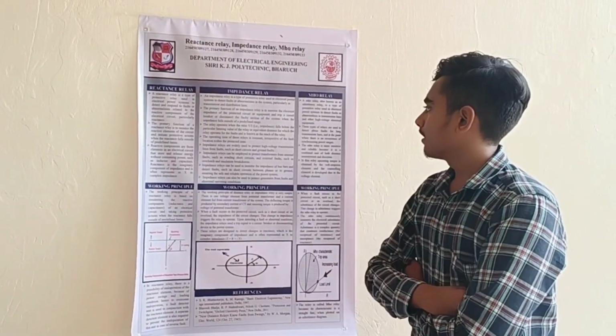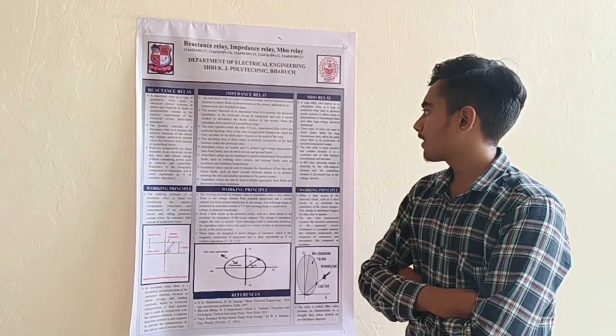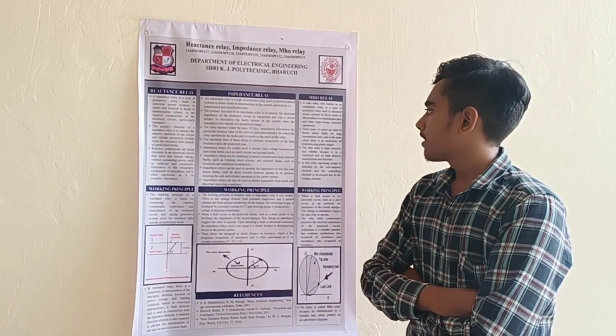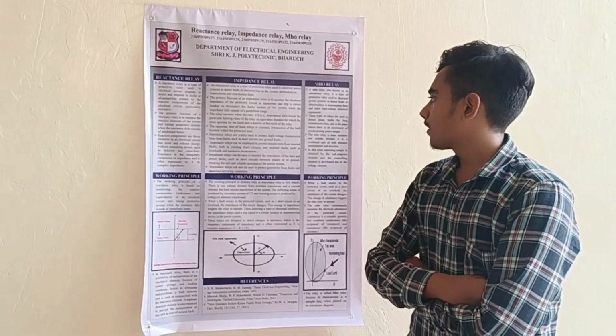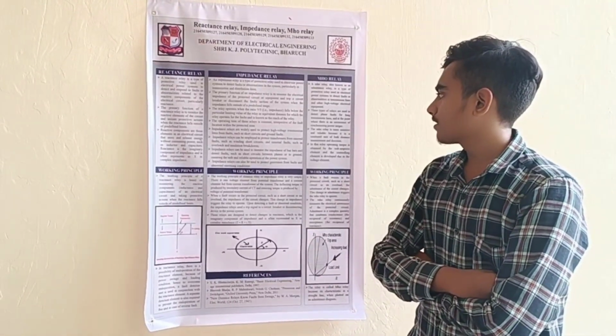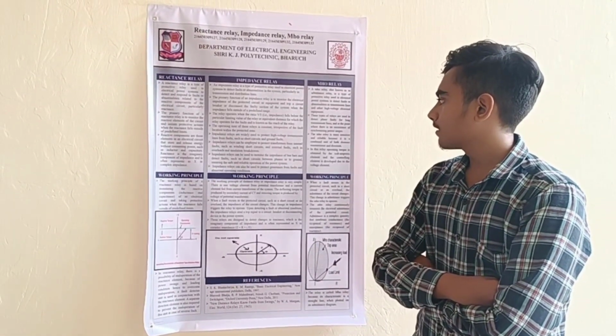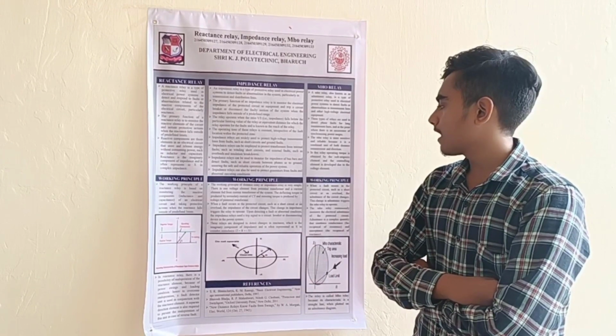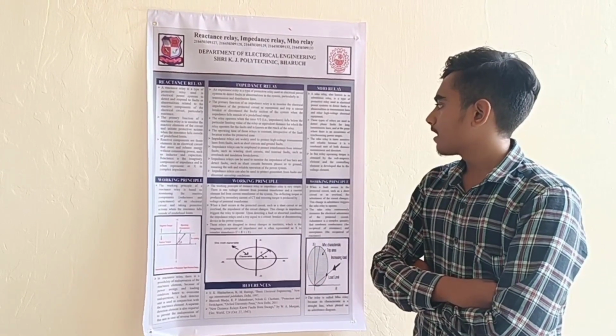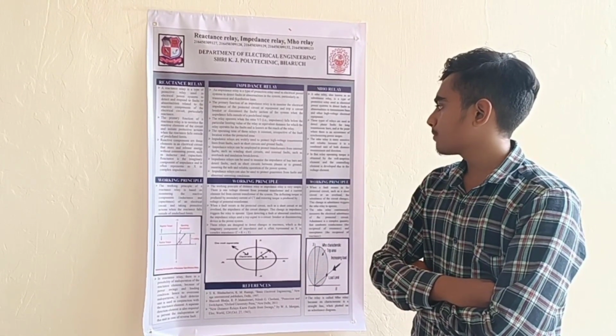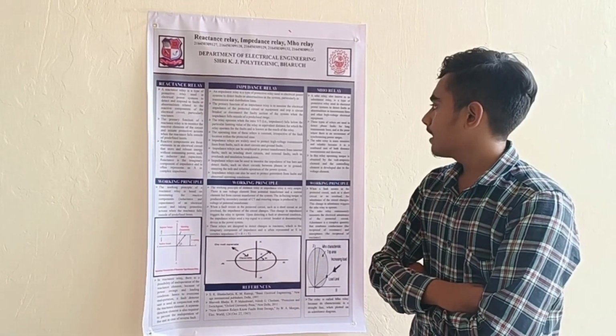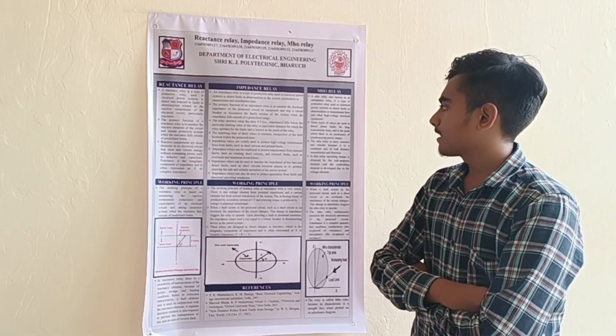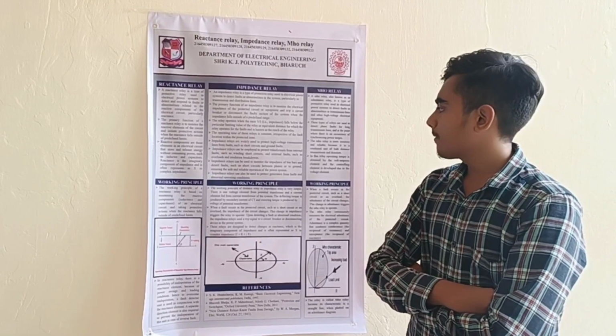It is used to detect phase faults for long transmission lines and at the point where there is an occurrence of synchronizing power surges. The Mho relay is more sensitive and reliable because it is a combined unit of both distance measurement and direction.